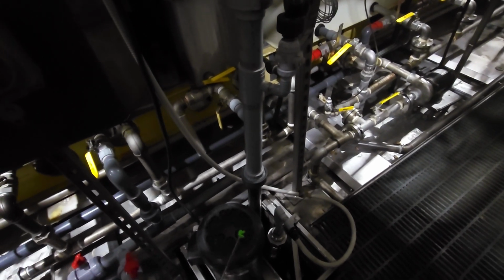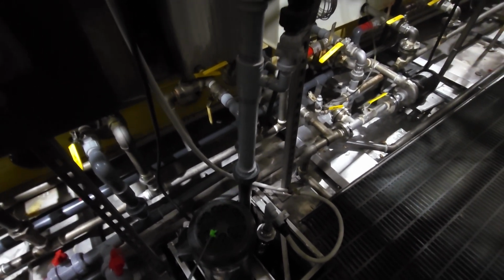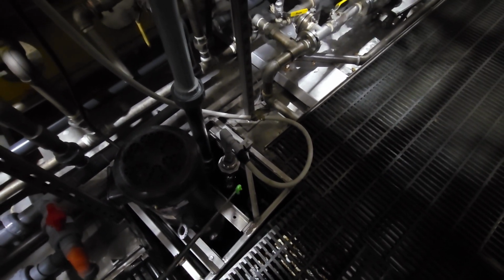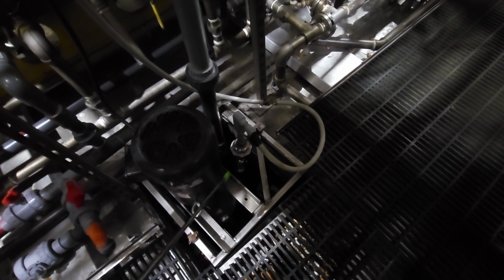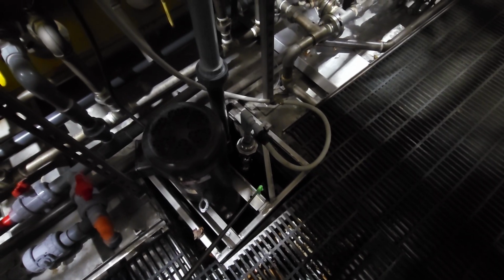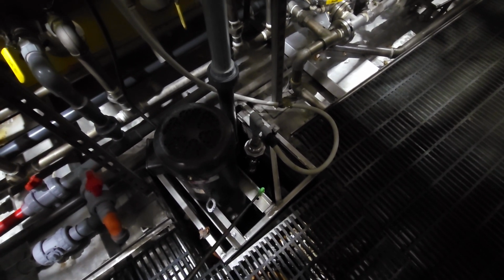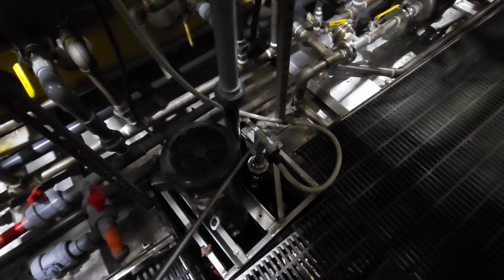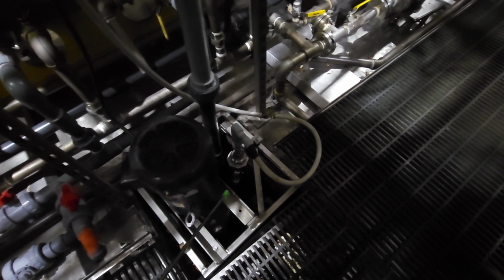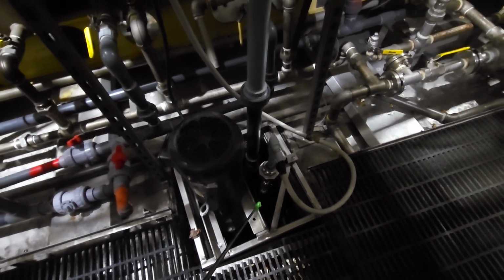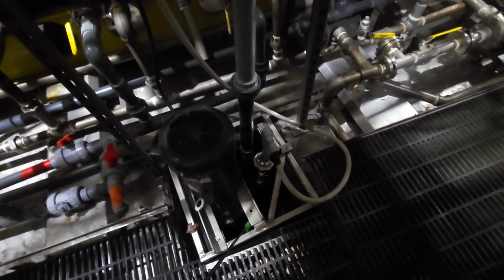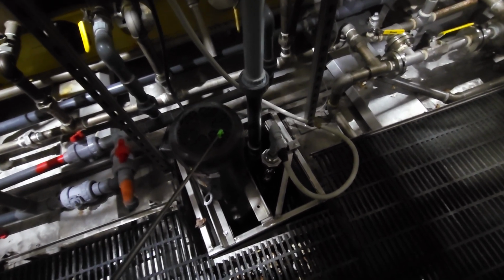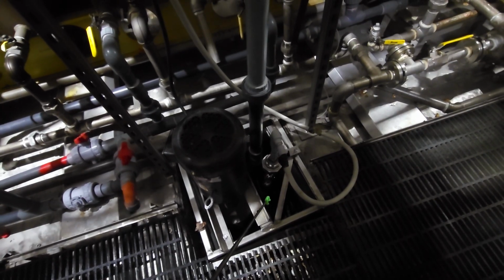Now say we are getting a code, you got to think about what controls the system. On this system here, it's a 3-ball check valve. I mean a 3-ball float system. Bottom ball tells it when it does shut off. Basically, it'll always be activated. Your bottom ball. Anytime any water gets in here, your bottom float ball will be activated. Once it hits that second ball, it'll turn your pumping system on and it'll run until the bottom ball turns off. That's how the system works. That way you're not just kicking on and off real quick. If you are kicking on and off real quick, that means your bottom float is not working correctly.